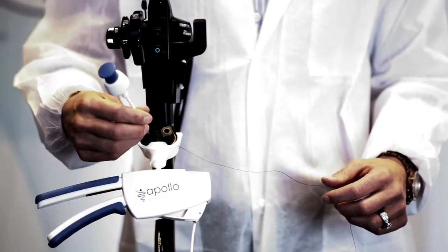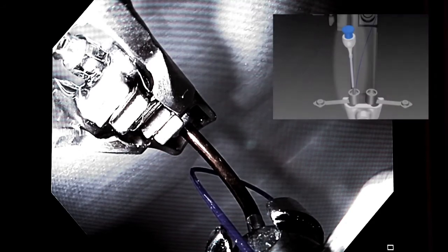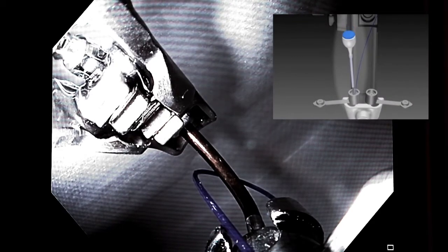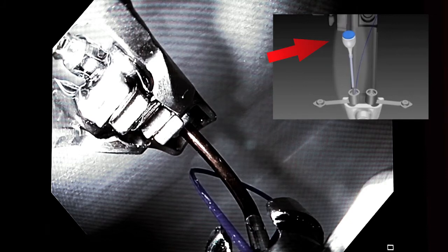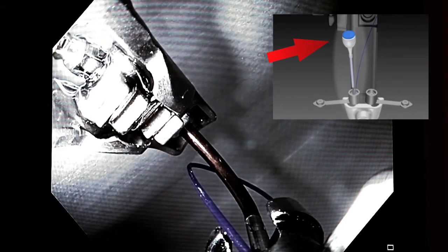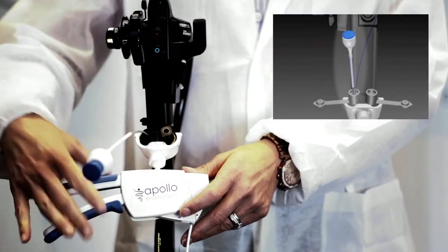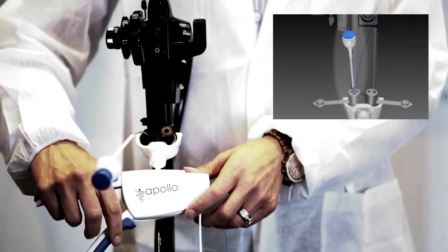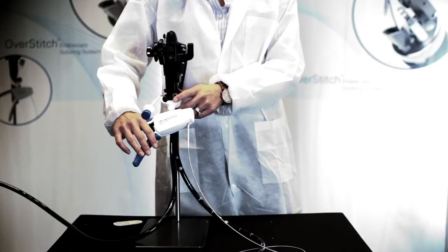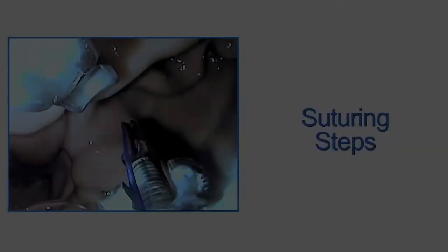Next, load the anchor onto the needle driver. Advance the anchor exchange catheter down the therapeutic channel. Once firm resistance is met, depress the blue button, and while holding the blue button down, pull the anchor exchange catheter back. Release the anchor exchange catheter and click the handle open. At this point, you're now ready to suture into tissue.